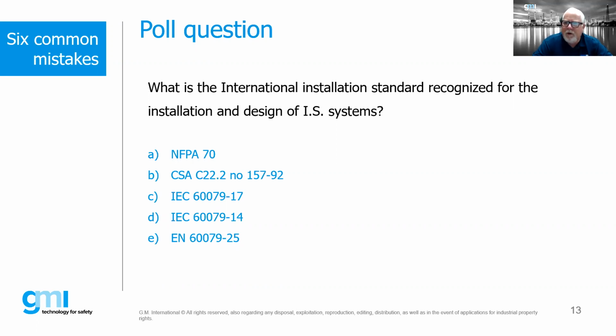We did have one question from Carl: if we follow 60079, are we compliant for installations in the US under NFPA? Yes and no. Ultimately we have to follow the NFPA 70 document for installations in the United States. The requirements within the National Electric Code, specifically all the details regarding installation and design of IS, fall within Article 504. That's where the meat of the installation details are located within the National Electric Code. There are a lot of similarities between Article 504 of the NEC and the IEC, but you ultimately need to follow the NEC.